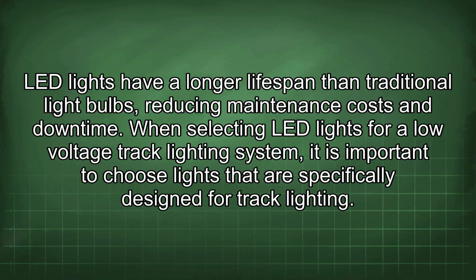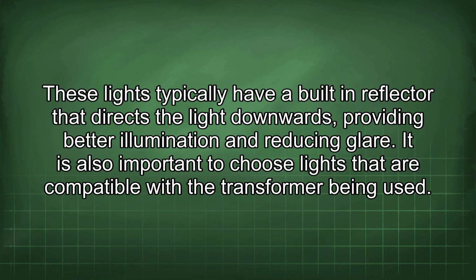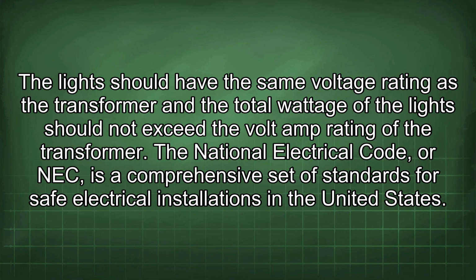When selecting LED lights for a low voltage track lighting system, it is important to choose lights specifically designed for track lighting. These typically have a built-in reflector that directs light downwards, providing better illumination and reducing glare. It is also important to choose lights compatible with the transformer being used: the lights should have the same voltage rating as the transformer, and the total wattage of the lights should not exceed the volt-amp rating of the transformer.